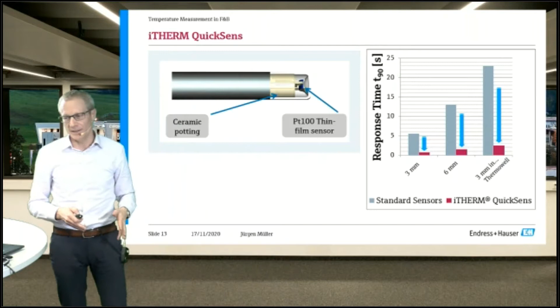If you look at a 6 millimeter sensor, you see in this graphic here, the response time is reduced even more drastically. And if you use the thermometer with a thermowell around the sensor to protect the sensor from the impact of the medium that you measure, you see in this graphic that a 3 millimeter sensor in a thermowell with QuickSens will have a response time of 2.5 seconds compared to normally 23 seconds. So this is really very, very good performance and very, very short response times that we offer here.